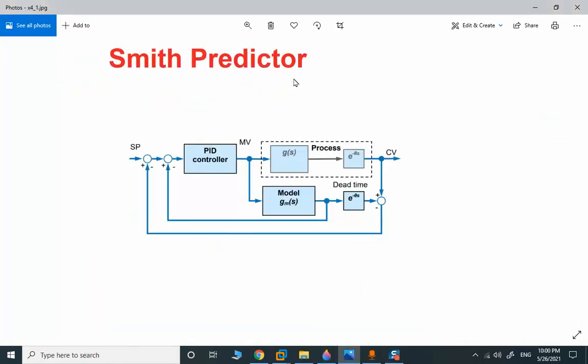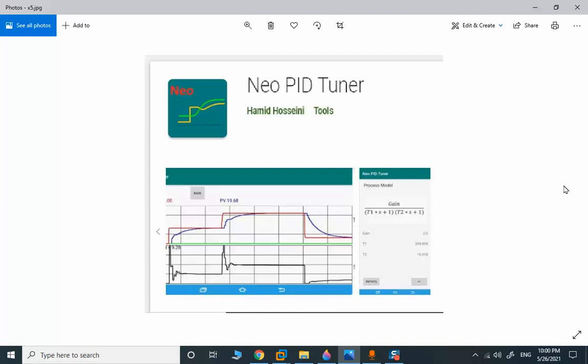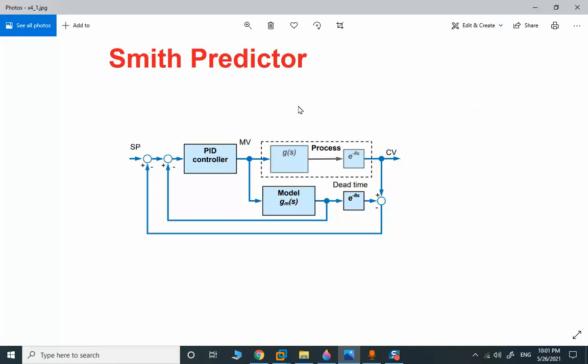Before implementation, we need a tool to estimate our process model. One offline tool I can introduce is the Neo PID Tuner — an Android application. It provides the time constant and gain for any given process model, and can estimate first-order, second-order, and in some cases higher-order process models. I will show you how I implemented this Smith Predictor in Delta V with a function test.